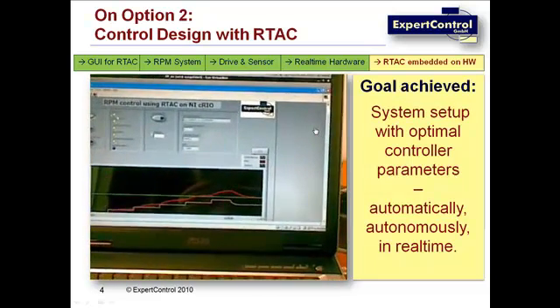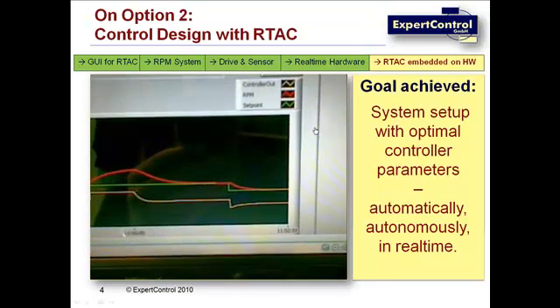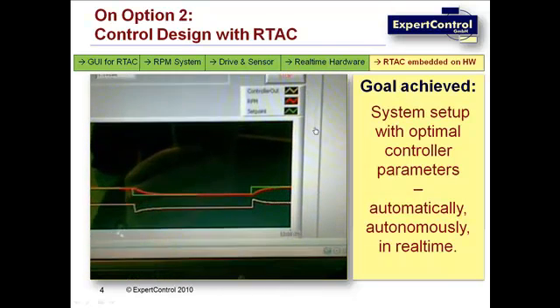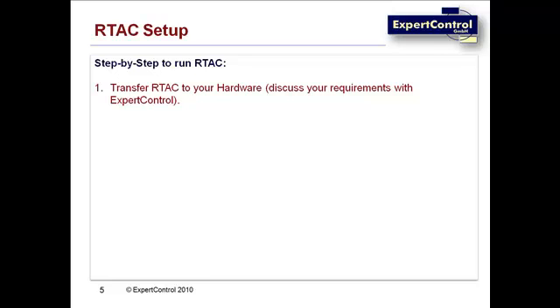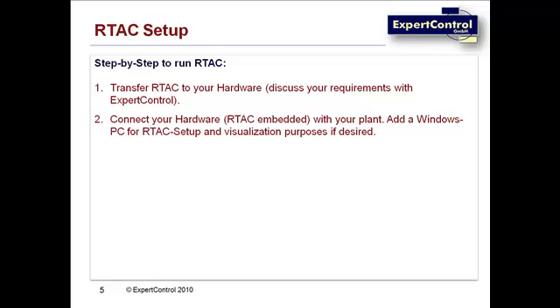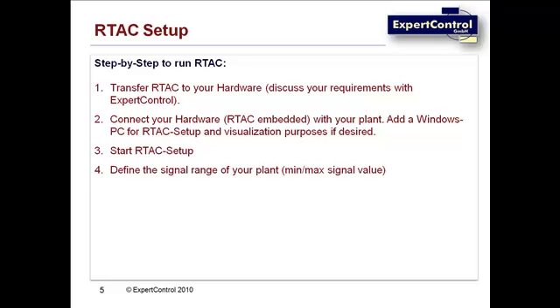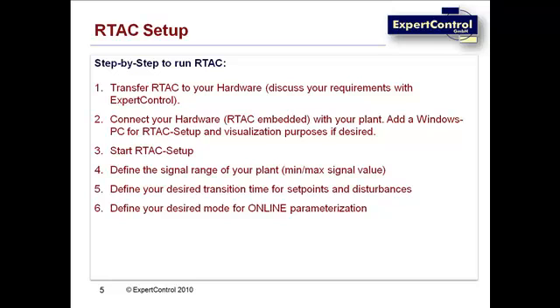All this has been done in one seamless step. Our apologies if RTAC was too automatic and too fast, but you can restart the video at any time. Here are all the relevant pre-processing steps for the user: first, transfer RTAC to your hardware — we will provide the suitable compiled object on request. Then connect your hardware with your plant and add a Windows PC for RTAC setup and monitoring. Start the RTAC setup, define the signal range of your plant, and define the desired speed of the final control system. Last but not least, you can define the desired mode for online parameterization. Then you are ready to run RTAC as seen in the video.